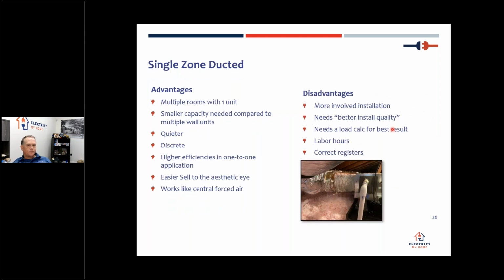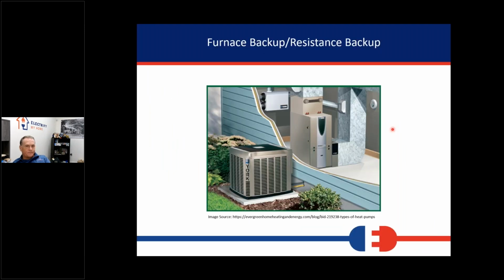That can be problematic. This is our favorite, single zone ducted. We can use a really small unit and do a whole house virtually. The smaller the units on these, the more efficient they are. We often put in just 18,000 BTU units for houses all the way up to 1,300 square feet. They're super quiet. We can tuck them away almost anywhere. They're very discreet, and it really presents like central forced air. And we use the right registers and design and all that, so we get really, really good efficiency and comfort out of these. The disadvantages: they have to be installed a little bit better, and you need to do a load calc for the best results on these and use the correct registers.